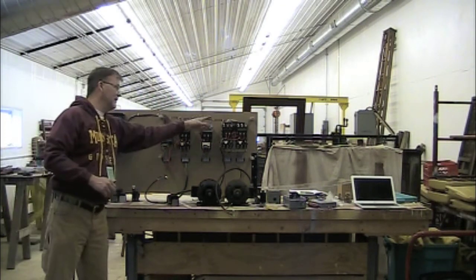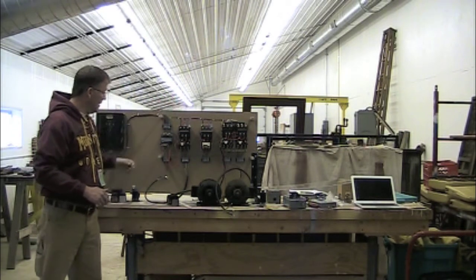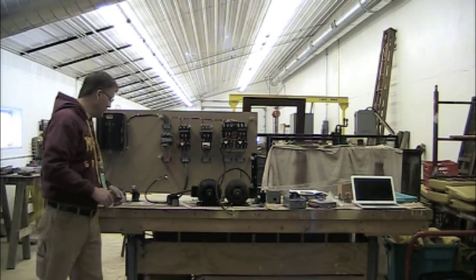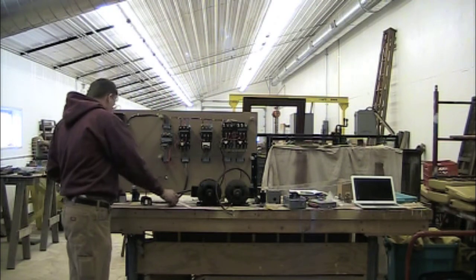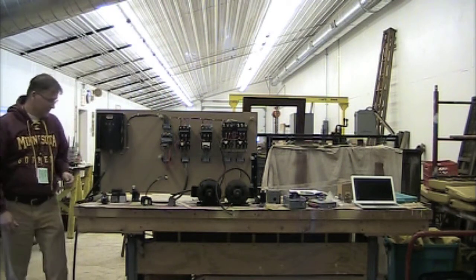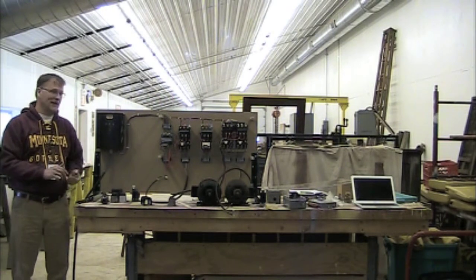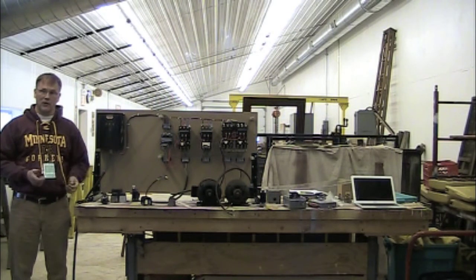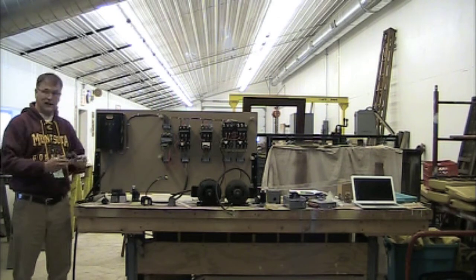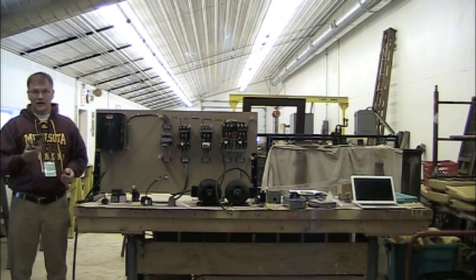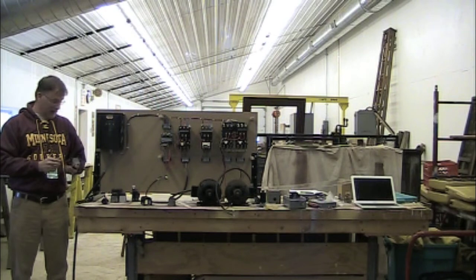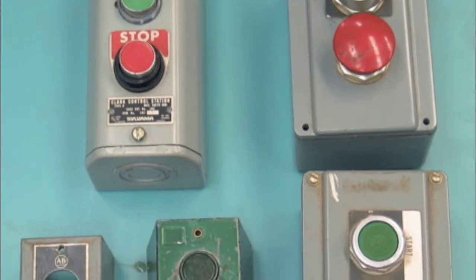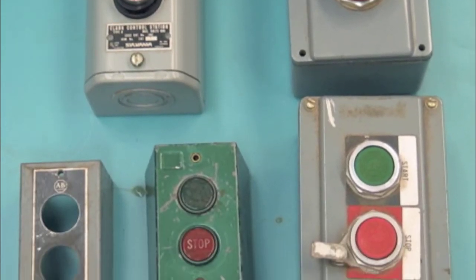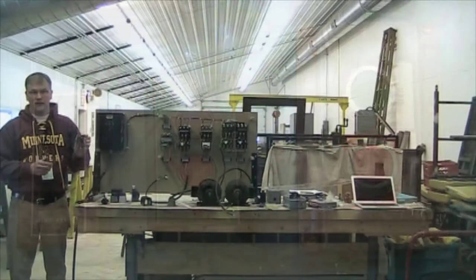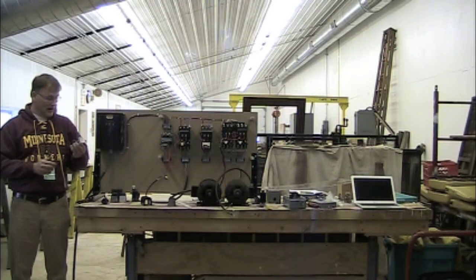3 phases coming into the top. So this is L1, L2, L3. And then they're wired through the bottom. So for most things on machines we're running with magnetic contactors, people are setting them up with what's called 3-wire control. So that's just your standard start-stop type station. And so these are all fairly generic from all the different manufacturers. These are old Allen Bradley ones, which are just integrated ones. They just are single function start-stop.